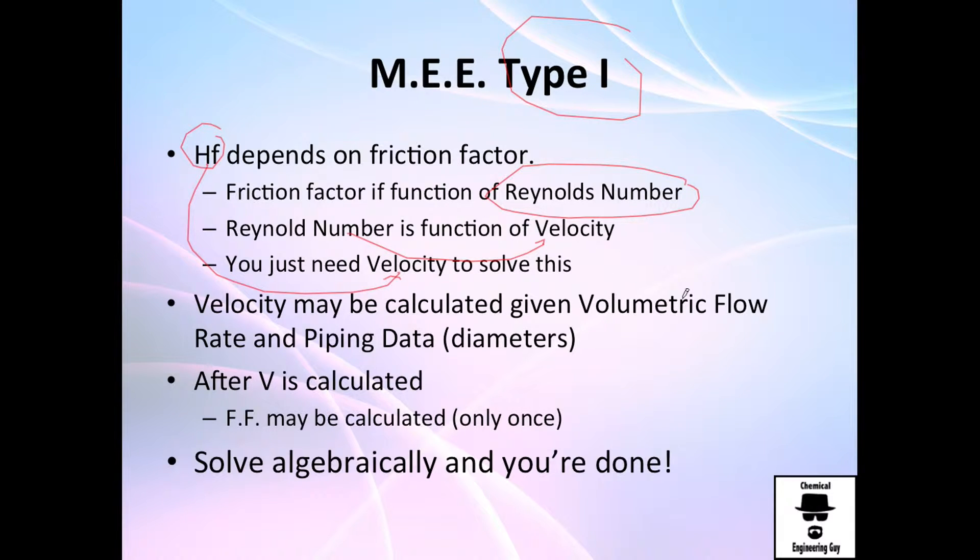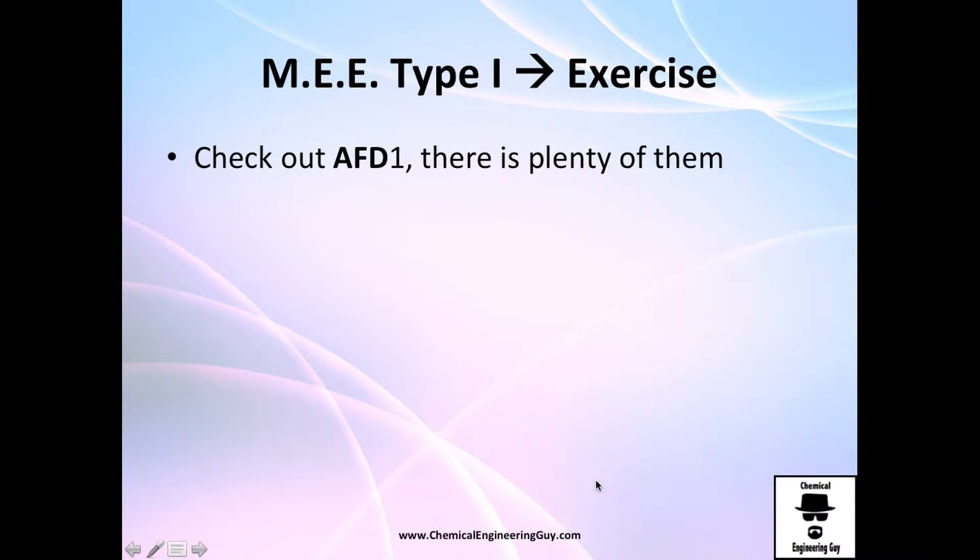Velocity may be calculated given the volumetric flow rate divided by the area of the pipe, and you have the diameters. You're probably going to have the data of diameters, you will be able to calculate velocity, and with velocity you calculate friction loss and velocity heads, and you can solve algebraically and you're set.